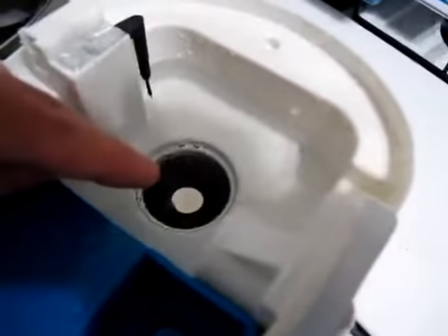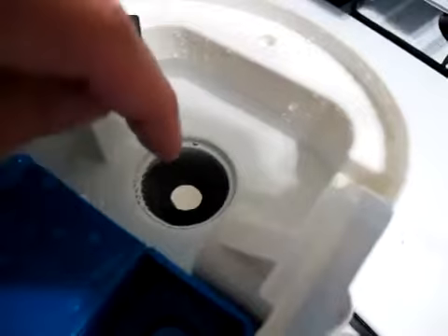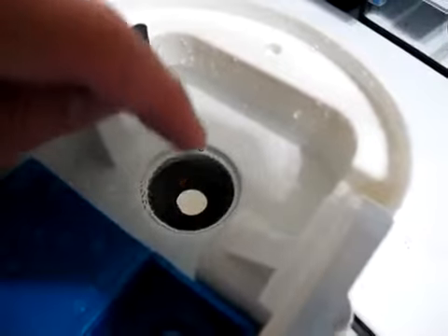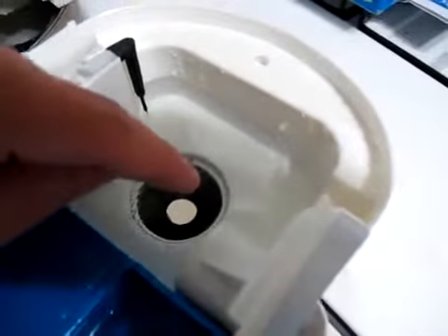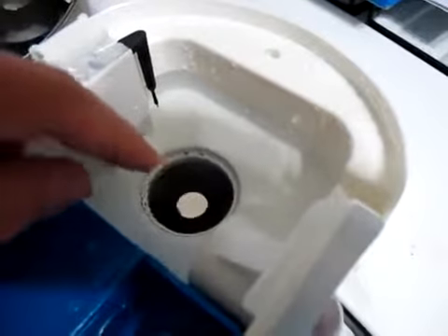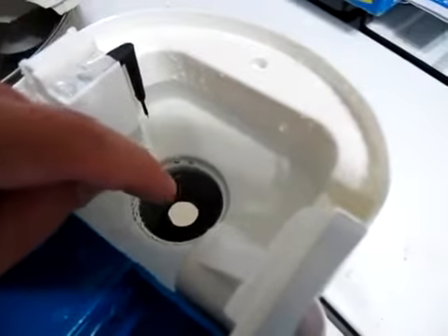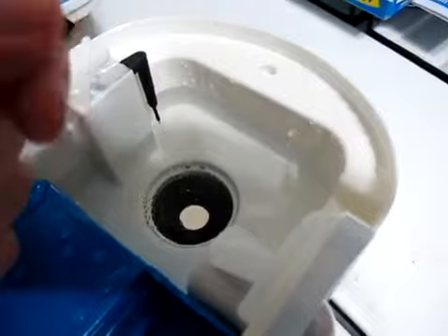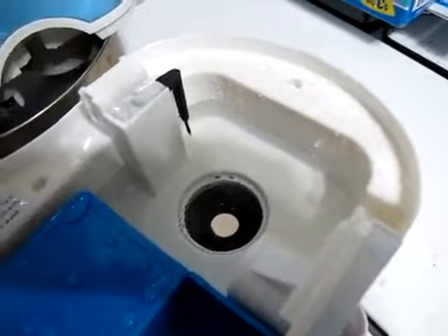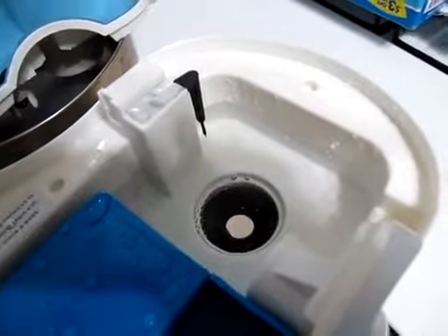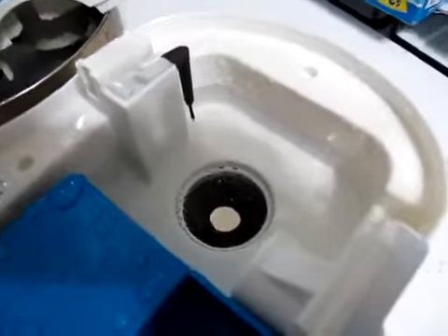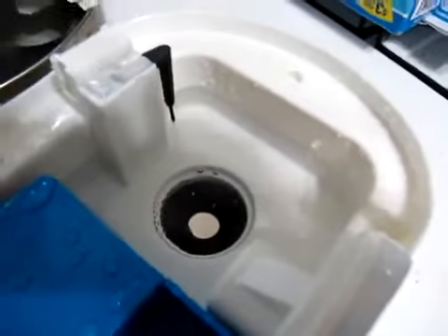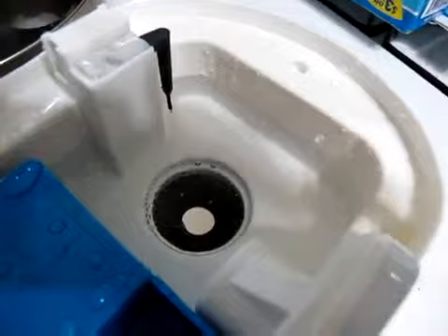One important thing is you do not want to touch the surface of that shiny piece when it's on, and you also don't want to run it without any liquid touching it, because that'll burn it up. If you touched it with your finger when it was on, it would burn the finger - not a heat burn, but an ultrasound burn, though it would feel the same. So it's not getting hot, but it's using sound vibrations, sound pulses.